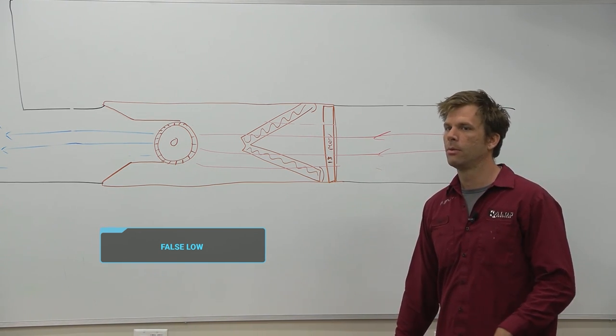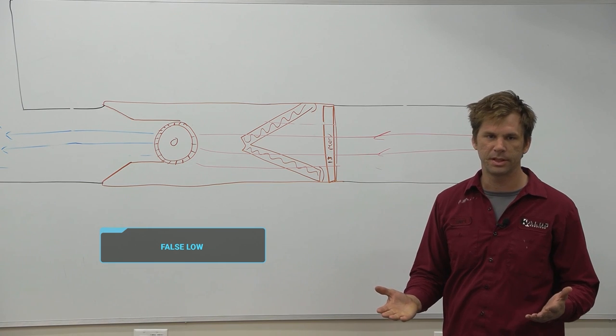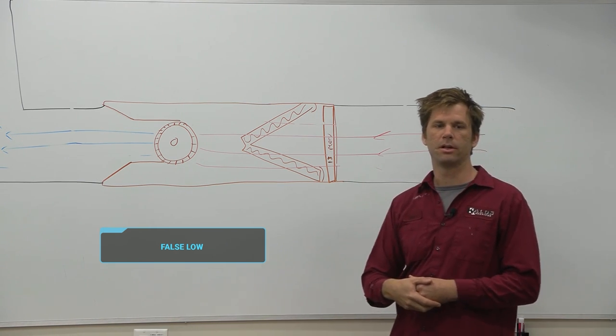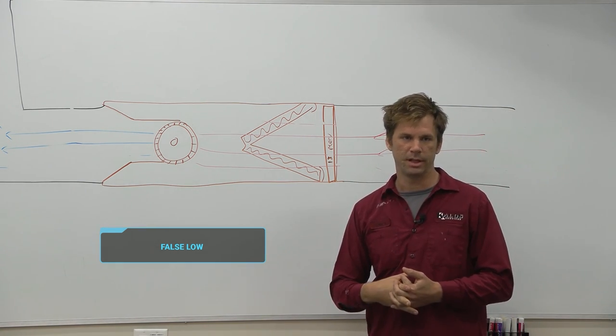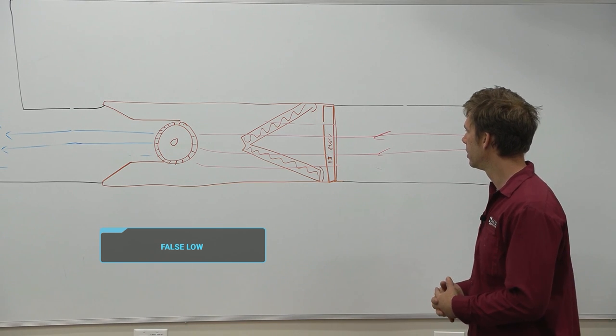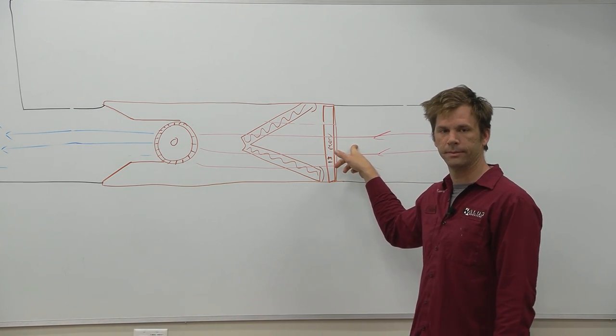If you take your probes and you measure here and here and you have a restricted filter or coil, you're actually going to have a nice really low static pressure reading. There's not going to be a lot of airflow here or here because of the restriction. There's not going to be much pressure, negative or positive, in your ductwork.